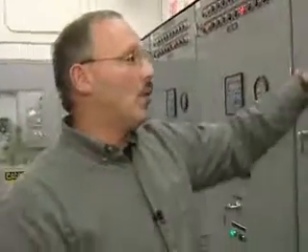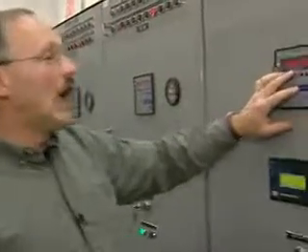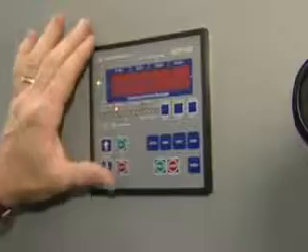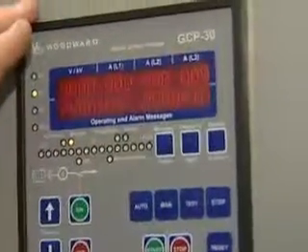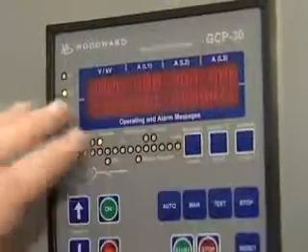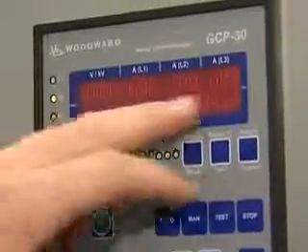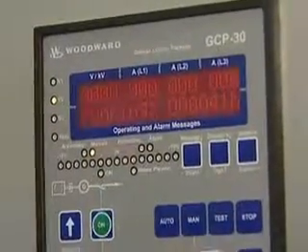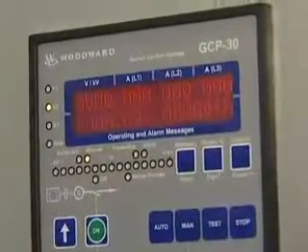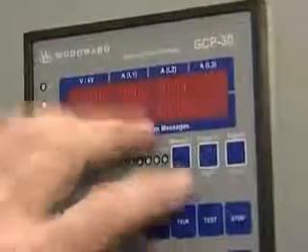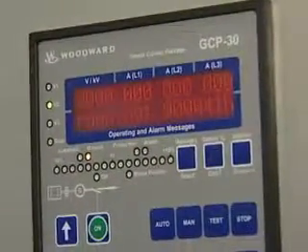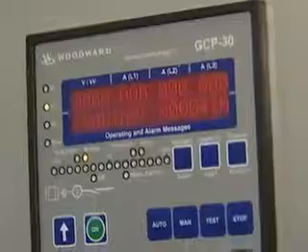One of the other important key things is engine run time. This will count down from 250 hours down to zero. Once it gets down to zero, a banner will appear saying 'service engine' — that's our oil change indicator. At 250 hours we change the oil. This will give you an indicator and a banner telling you that you need to be changing the oil in that machine.